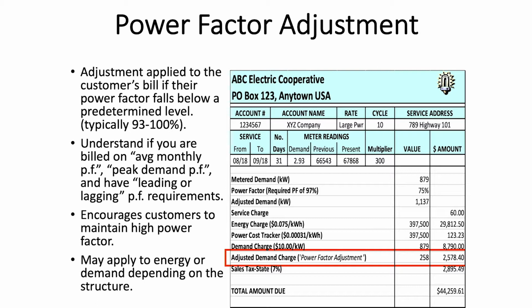It's an adjustment applied to the customer's bill if their power factor falls below a predetermined level, typically 93 to 100% for the co-ops and Hoosier system. When I started in the industry, those numbers were often in the 80 to 85, 89% range. So over my 35 years, the threshold has been creeping up because power factor is becoming more important. Understand if you're billed on average monthly power factor or peak demand power factor, or if you have a leading or lagging power factor requirement from your co-op.